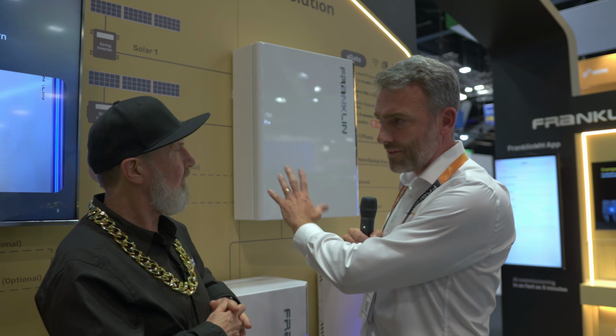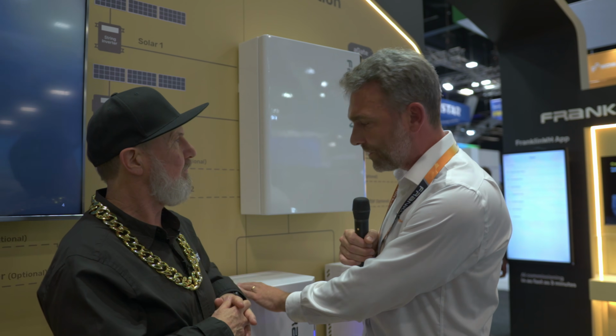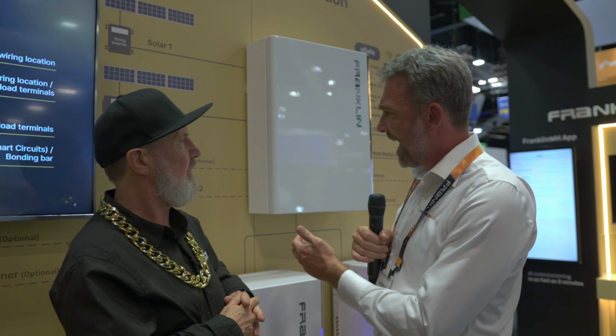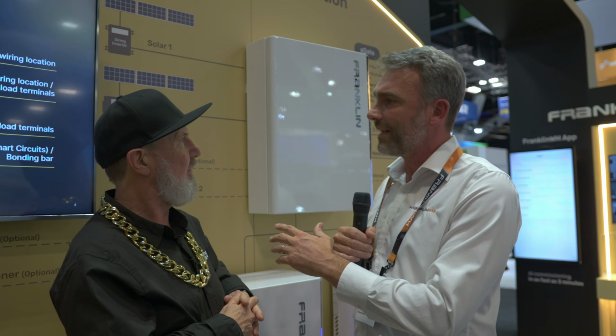Has it also got any communication functions? Of course it does - the gateway is sort of the site manager. It will talk to all the A-Power batteries over CAN bus, control those for your self-consumption or your time of use. And in terms of controlling PV inverters, we don't need to do that during grid-tied situations, but once we're off-grid, we employ frequency shift and also binary control via the integrated relay.